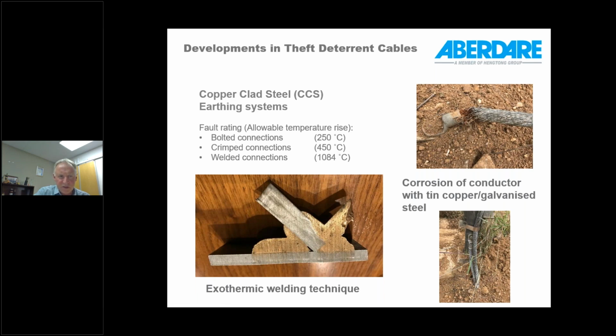So the best connection, really, that will take you up to the melting point of copper would be a welded connection, like an exothermic weld connection like you see here. But you can also obviously get bolted or crimp connections, but one would have to consider that the fault rating of those conductors would be lower than for an exothermic weld connection.